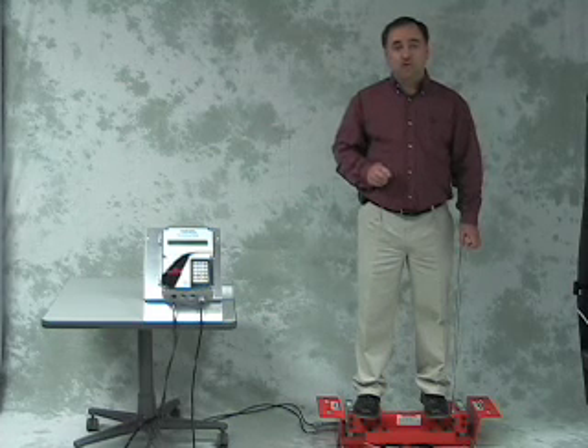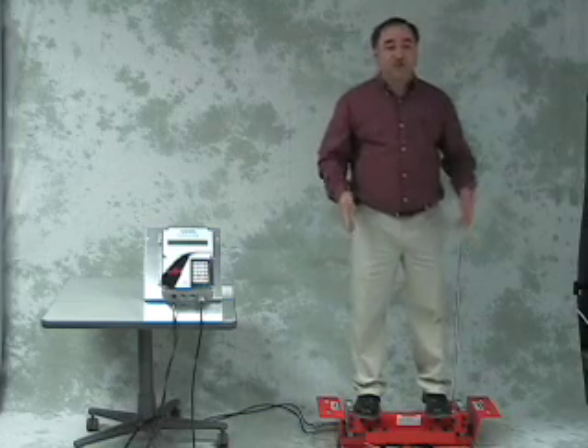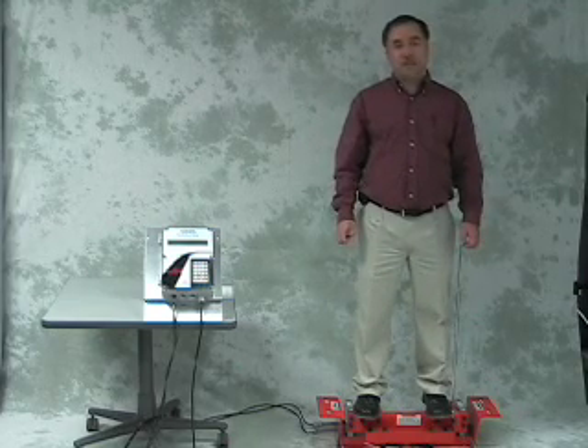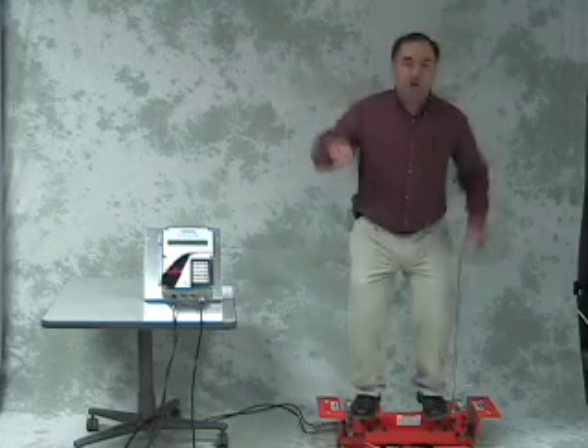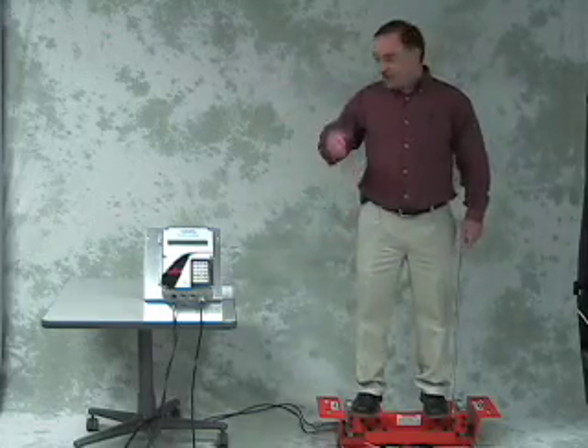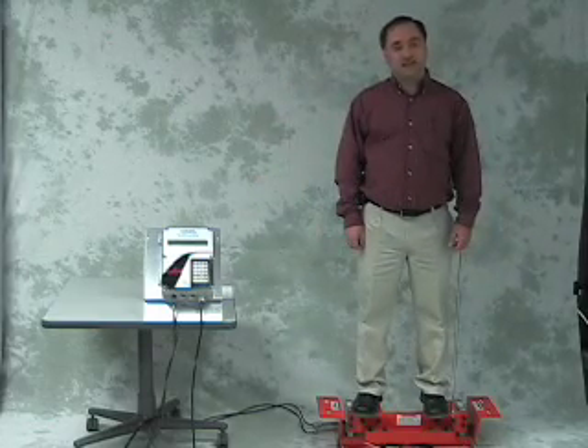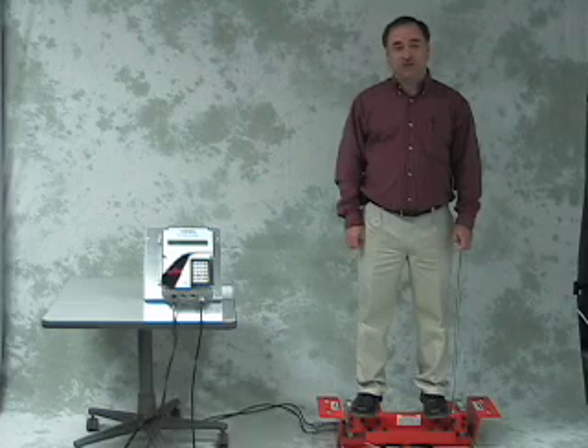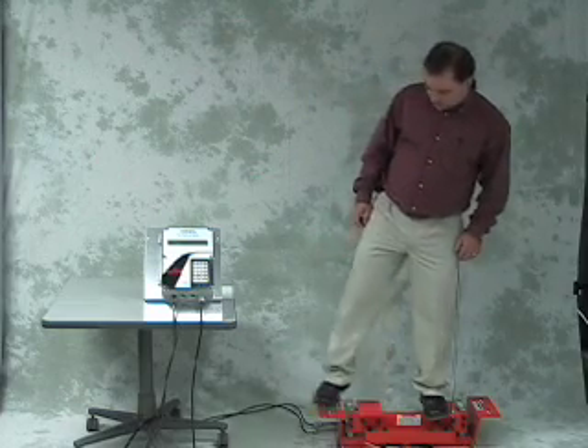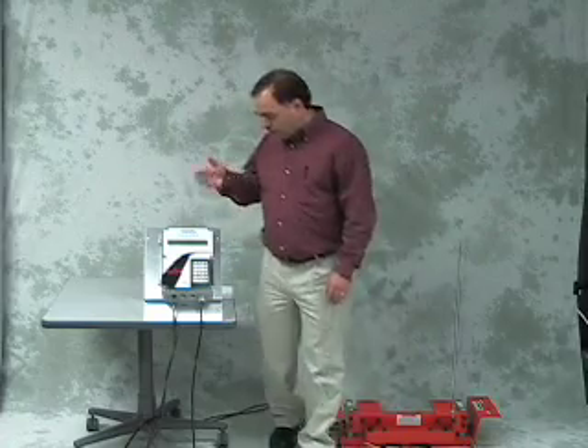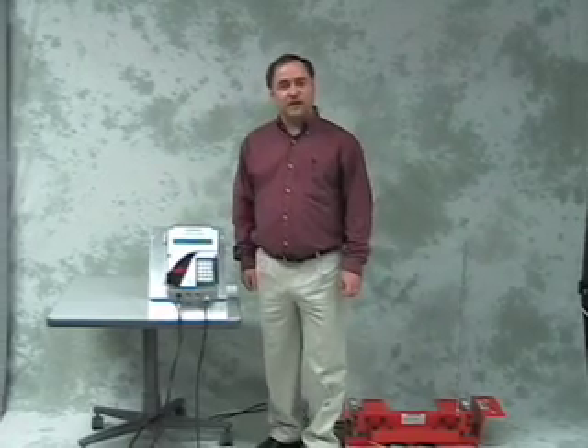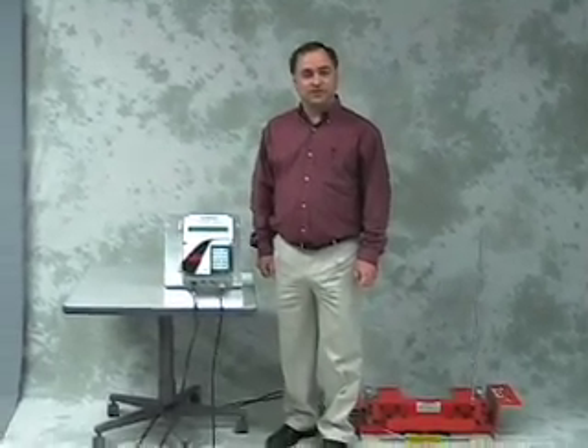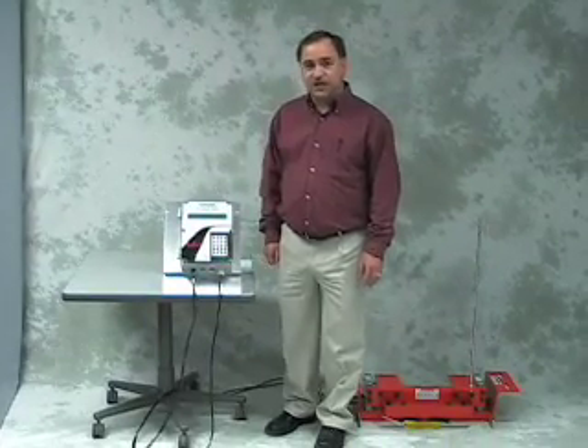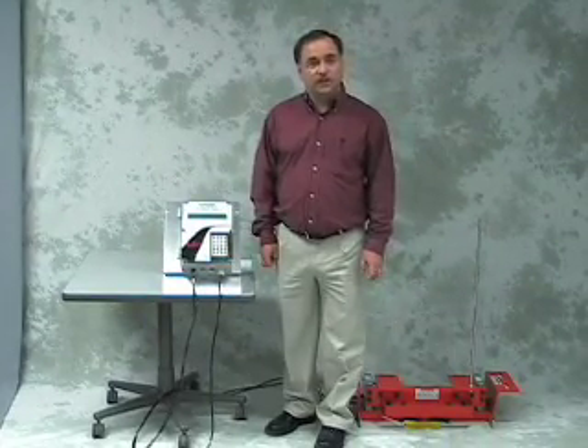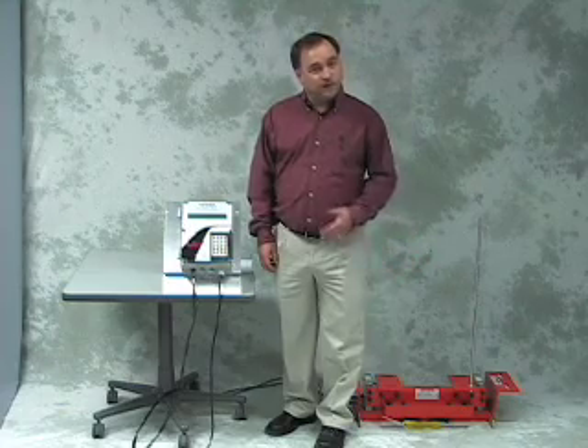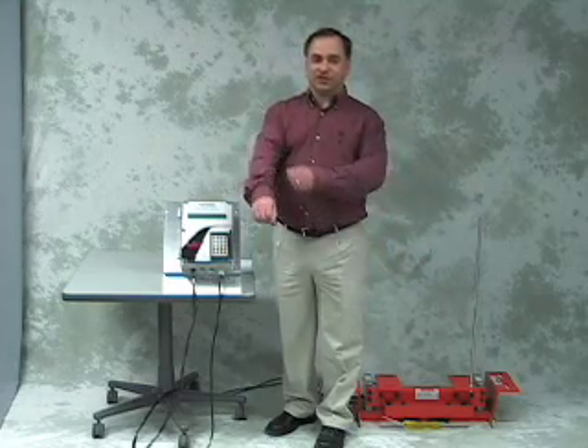Most of your customers have been told never to stand on a scale. Imagine what they'll think when you start to jump up and down on the scale and read the display and see that it has no difference in the reading than it did before. You can then get off the scale and the scale will return right back to reading 0 kilograms. The customer has now seen that this scale can weigh a person fairly accurately. Have the customer stand on the scale.